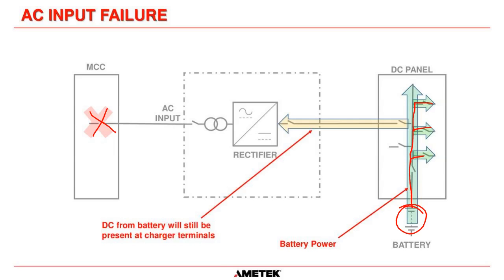But do bear in mind, obviously, if you've lost power at the MCC, this breaker here is going to be closed, and this breaker here is going to be closed. So don't think that you will have no power in your rectifier on its output terminals. There will be a backfeed from the battery into the charger. There'll be no power draw, but there will be backfeed on the positive and negative terminals in the charger in that situation.